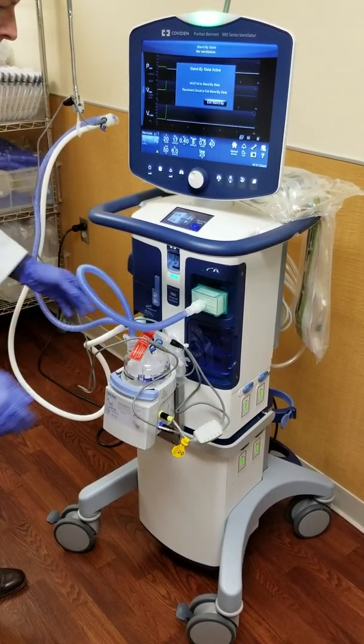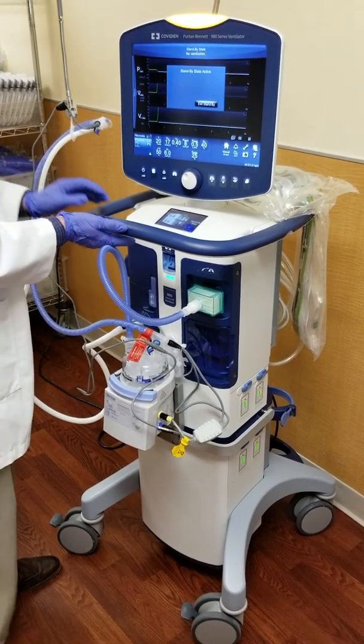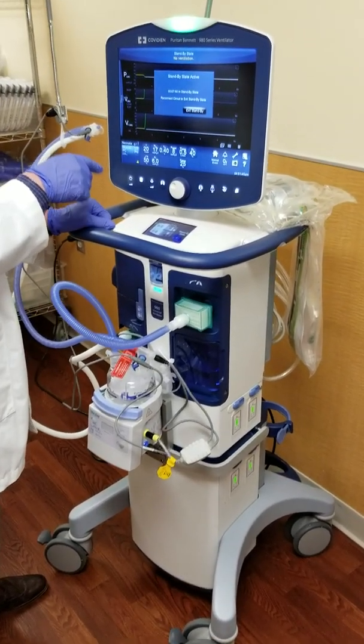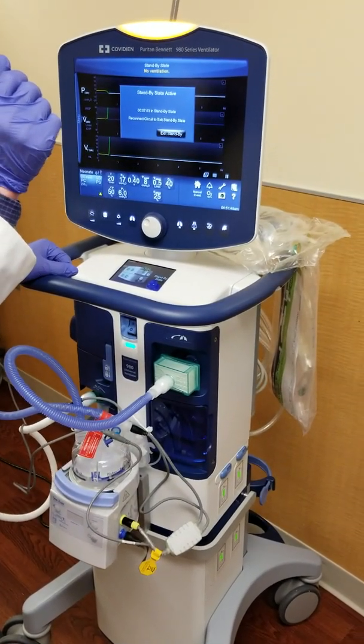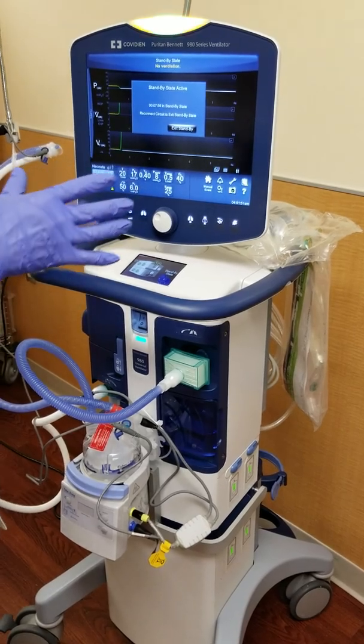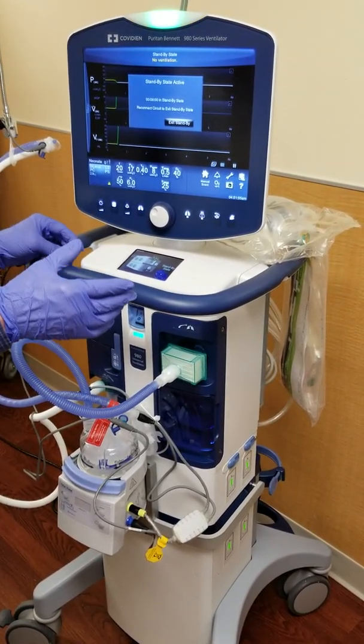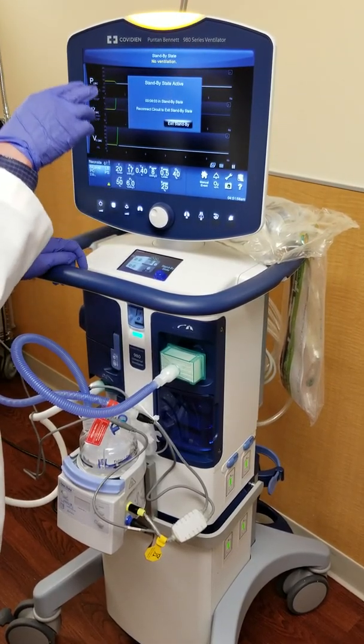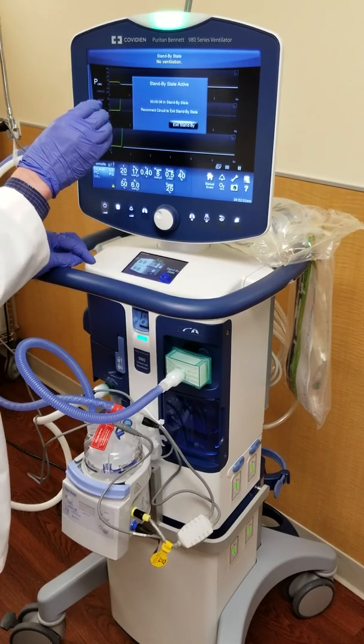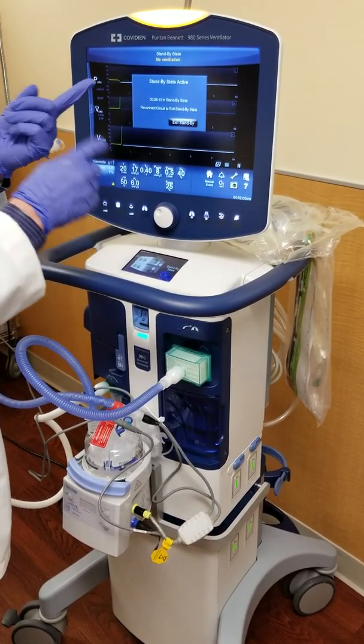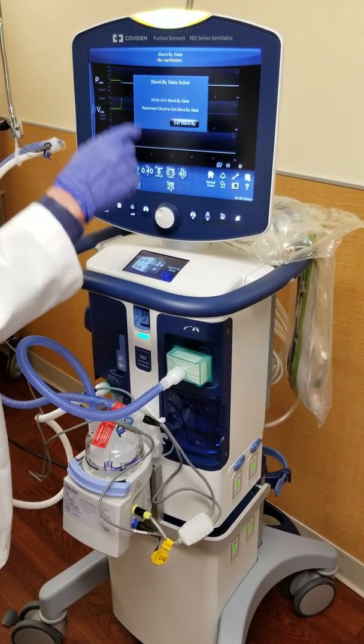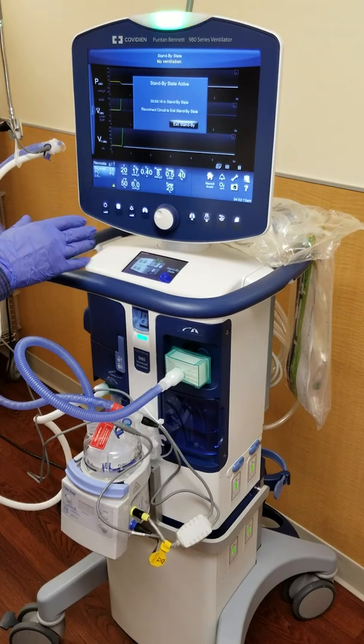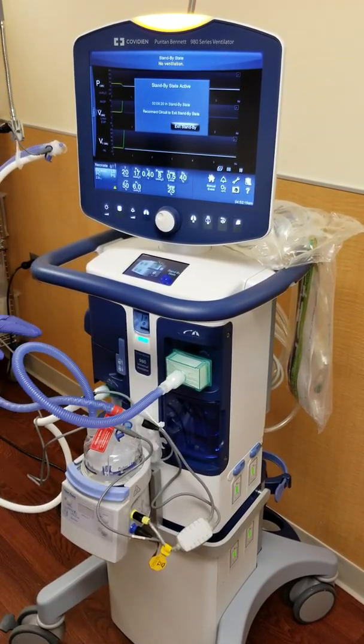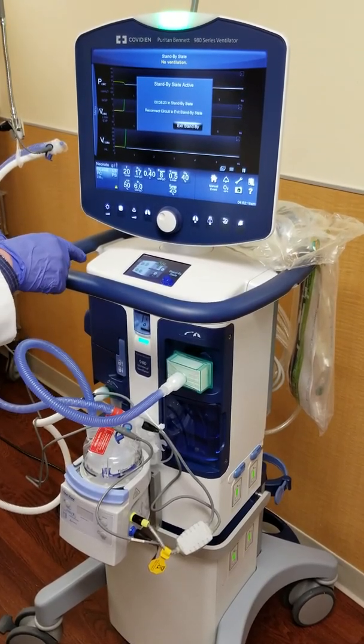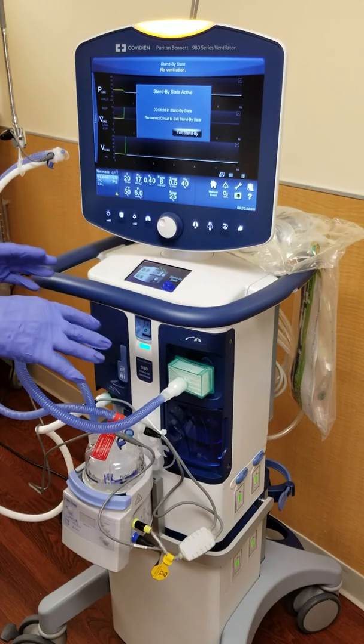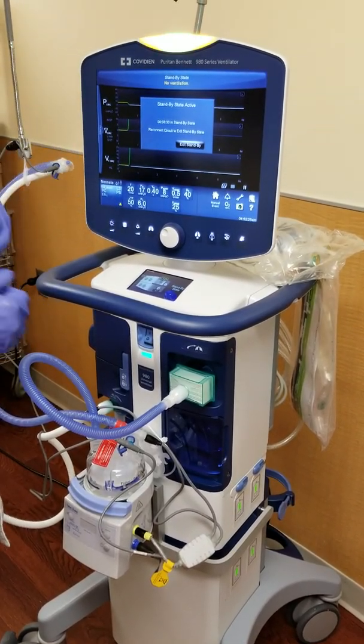We are all hooked up, used a couple adapters, changed the door, changed the filter. You're going to fire it up, and you're going to run an SST. Short self-test, and you're going to keep accepting and go into a short self-test. And for the time constraints, I'm not going to do that since I did that in part 2. And then at the third step in on your short self-test, it's going to give you the option of the adult, pediatric, or neonatal. You want to select neonatal and then go ahead and perform the SST. And that's how you get this set up. Get some adapters going, change the filter, change the door, start an SST, run it as a neonatal, and it's pretty similar to the adult. Read what it's asking you, perform the intervention.